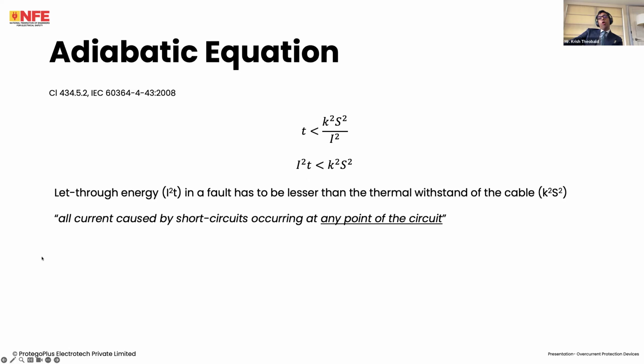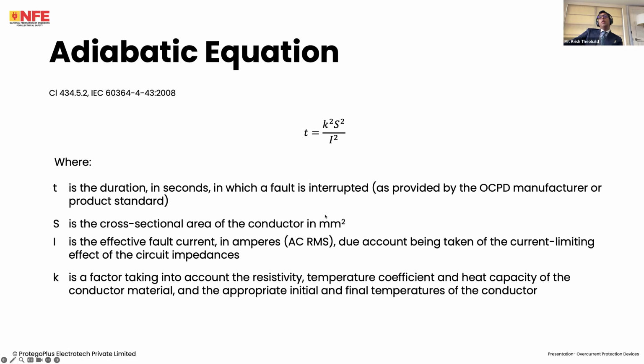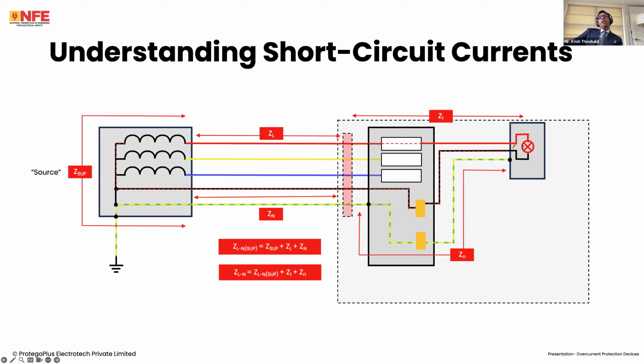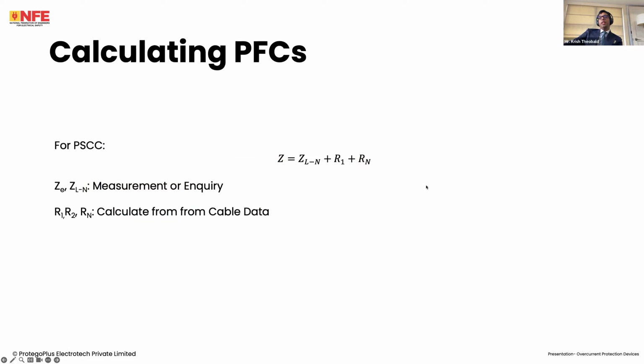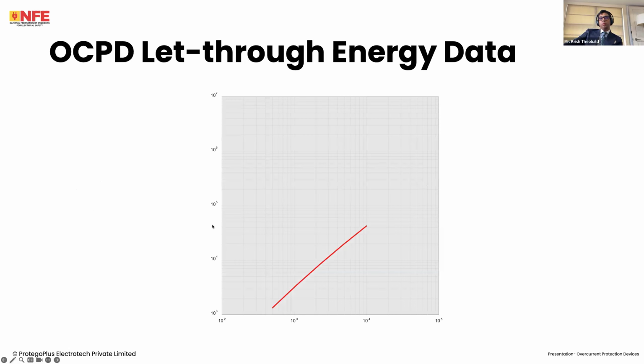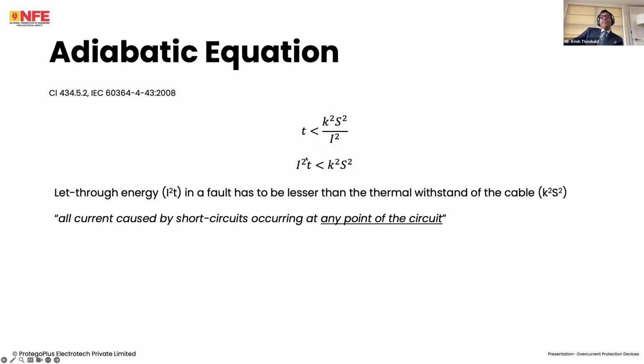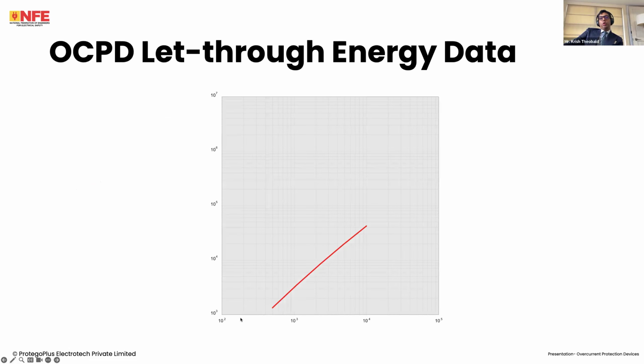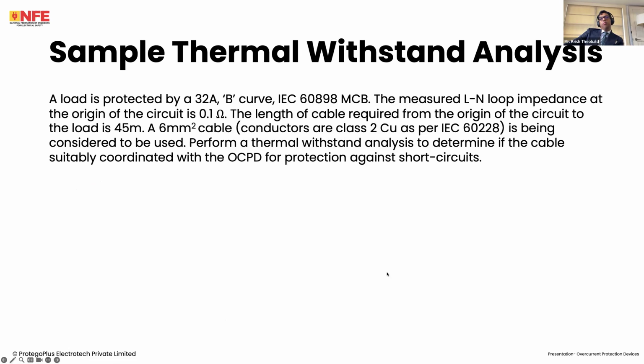Remember, all this is for all short circuits occurring. So, for earth fault loop impedance, we only considered the fault here. But for short circuit withstand, we need to consider all values. And the best way to do that is graphically. Like I said, manufacturers will give you this I squared T graph, showing you for this amount of fault current, this is the amount of I squared T.